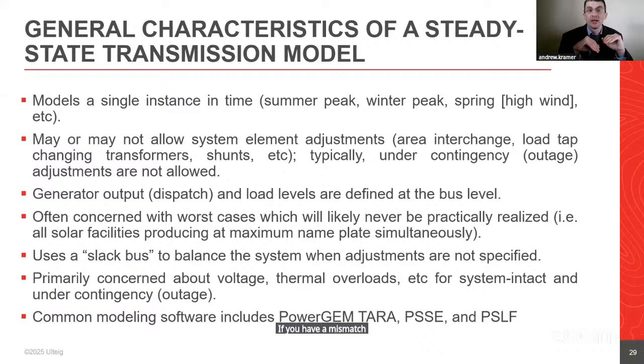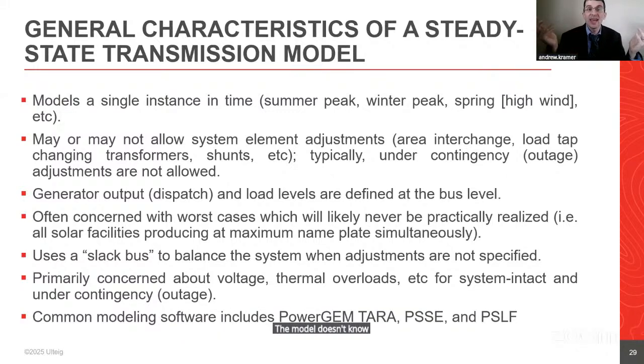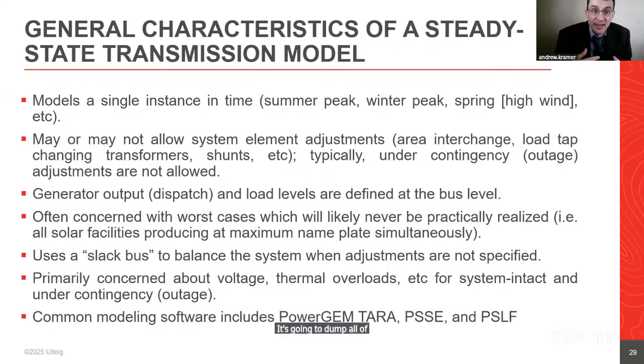There's something called the slack and swing bus in these models, which is kind of a catch-all. If you have a mismatch between generation and load, it's not like the economic models I run where it's just going to move the generators up and down. The model doesn't know what to do, and it can't just leave generation and load mismatched with an energy imbalance. It's going to dump all the excess energy into the slack bus, also called the swing bus, or pull generation in from the swing generator. They're usually denoted as one and the same, slack and swing. It's kind of a rookie mistake, which is amusing.